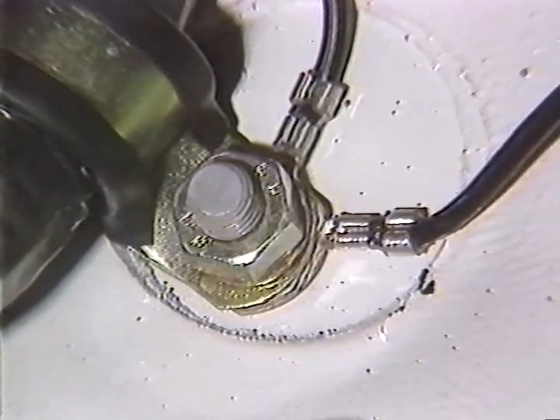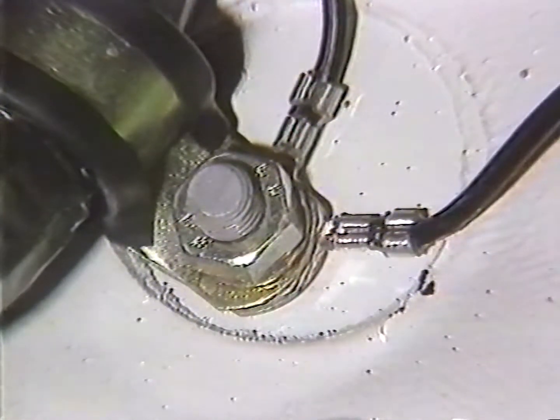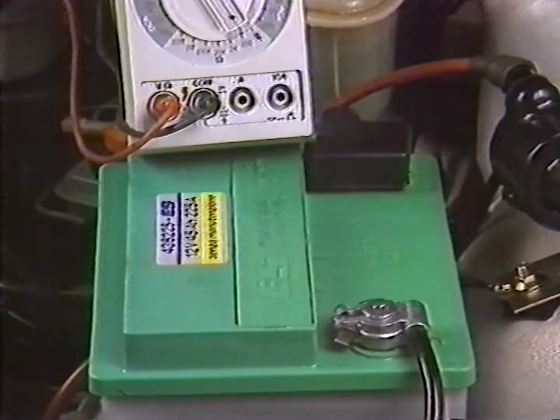If the earth is oxidized, instead of giving zero potential, it gives a greater value, this value being subtracted from the capacity of the particular item of electrical equipment, which will operate either less efficiently or not at all. It is as if we'd inserted an extra resistor in our circuit. It's very important to remember that if there are variations in the value of the earth, we will not be able to have a stable supply value.